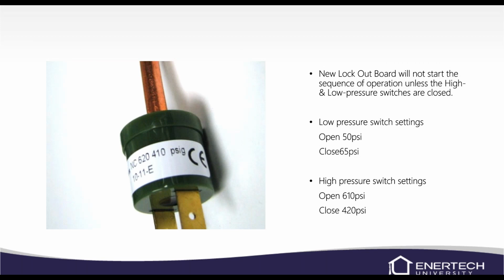So on these newer lockout boards, there's a little bit of sequence that's changed, some logic. One of the things that has changed is that on this newer board, if the low or high pressure switch are open when the Y call comes into the board, the unit will not try to start. So we obviously don't want to run it in a high pressure situation, and we don't want to run it without refrigerant in it. So if either of those switches are open when the call is received, the unit will immediately go into a lockout.